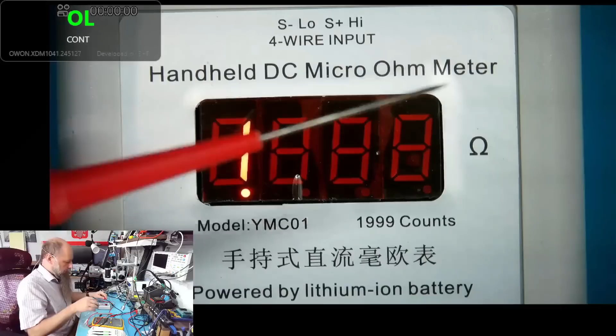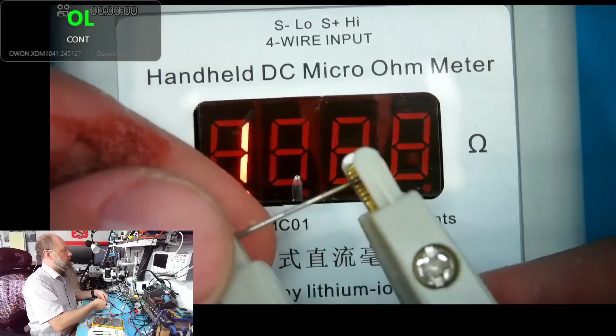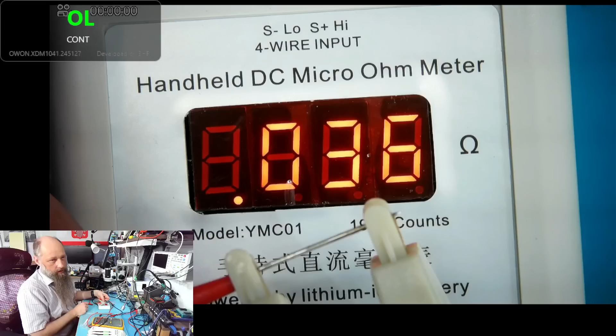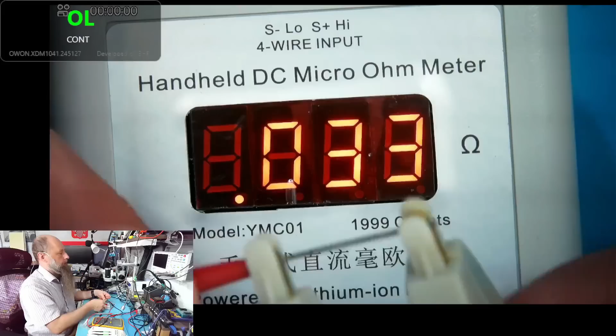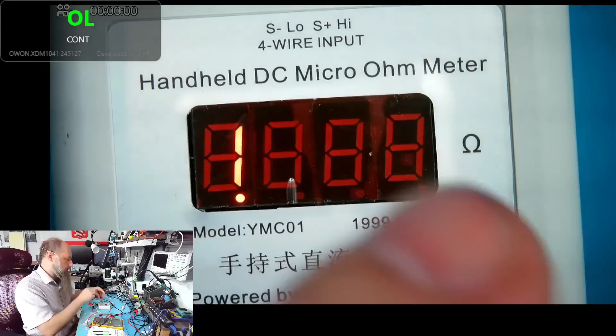For reference, if you think that's not a big deal and it will always show 0 - this is stainless steel, rusty stainless steel. It doesn't rust, but it accumulates gunk on it, and that shows us 36 milliohms. That's huge for such a short distance, but it's mainly the oxidation on the surface of the metal, not the resistance of the metal itself. But that's how we measure - that's what we touch to the circuit to measure something.